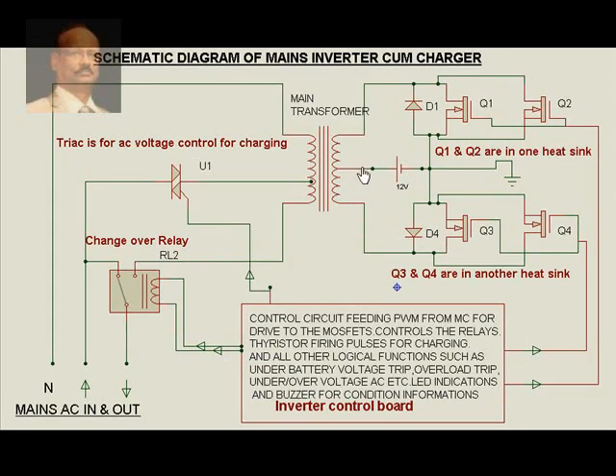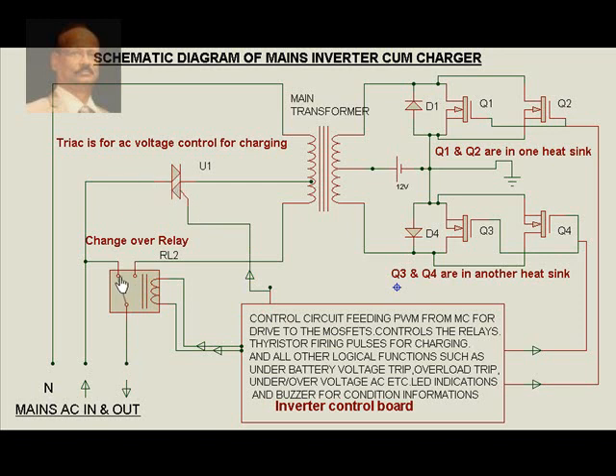The power developed is an AC voltage, and that AC voltage is stepped up by the transformer. In this case, the low-voltage side is the primary and the high-voltage side is the secondary — the reverse of mains operation. At that time the relay contact switches over through the control circuit, so the inverter output is now available. This point is disconnected from the mains because the relay has switched over, ensuring mains is not connected during inverting operation.